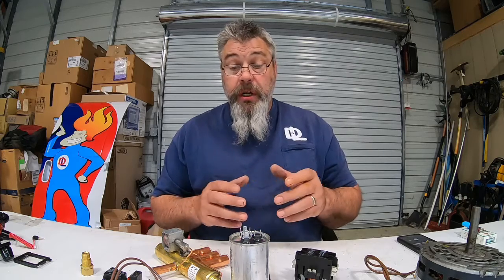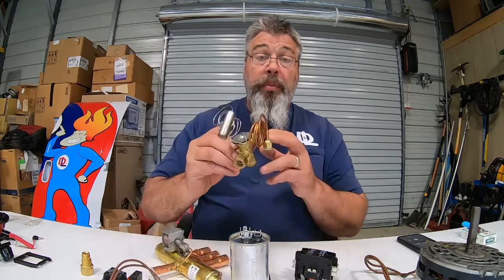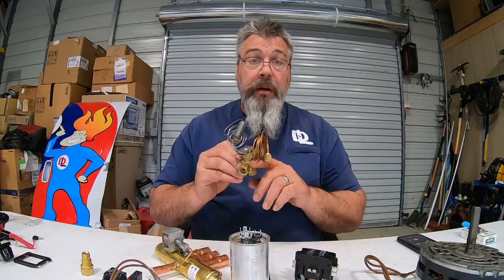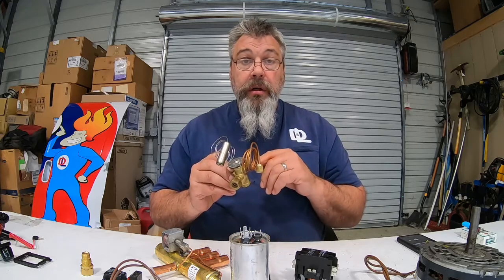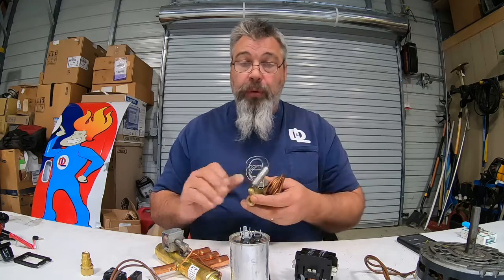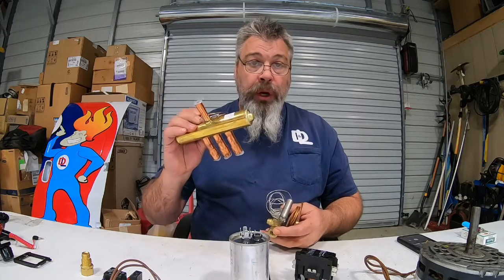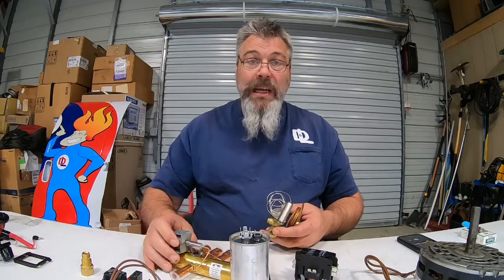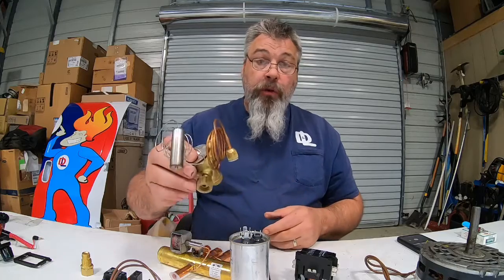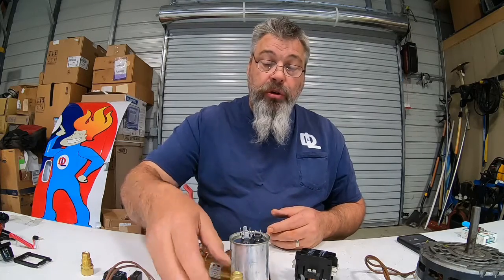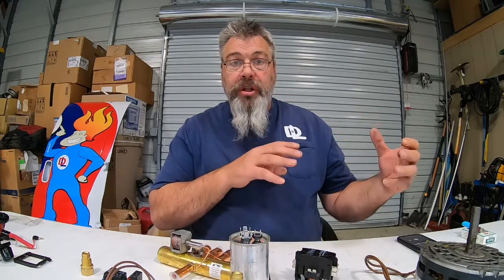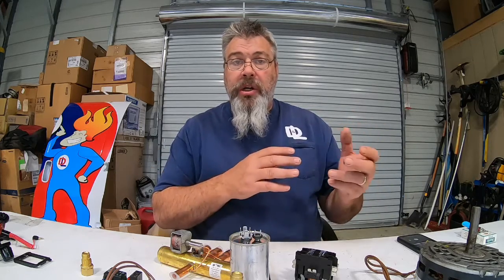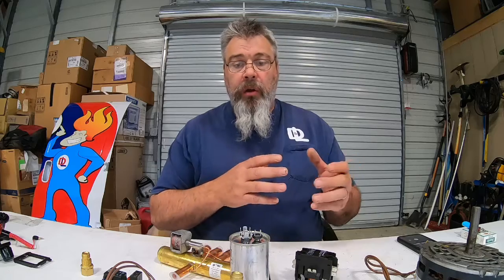What it does is, and that's where these metering devices come back into play, when we change the state from a liquid to a gas, we then allow it to go back through the reversing valve and into the compressor to be recompressed. That's how we get our heat from our refrigerant. We compress it, we transfer the heat from the outside into the condensing unit. We'll pull the heat out of it in the summertime. We're pulling the heat out of your house.